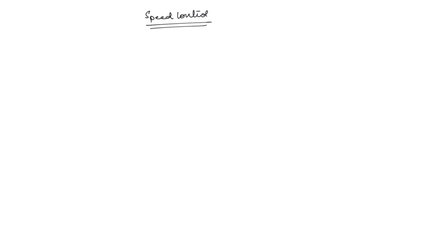So what is the expression of speed? N is equal to (1 minus S) times the synchronous speed. So if we have to control the speed, then what are the two parameters available to us? We can control the slip or we can control the synchronous speed. Now synchronous speed in turn, it is dependent on what? The frequency and the number of poles.